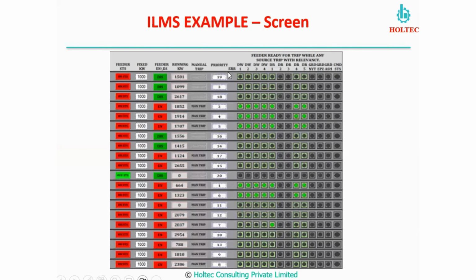And these are the predefined operating scenarios. Suppose we have priority number 3, but in some operating scenario this is not activated. So the activated load shedding breakers in each scenario are these only. This is something which will be available for us. So we know what is going to happen in our system if any abnormality occurs in the system, and we can decide the priority, which load we have to sacrifice.